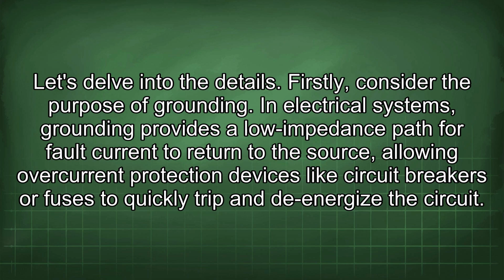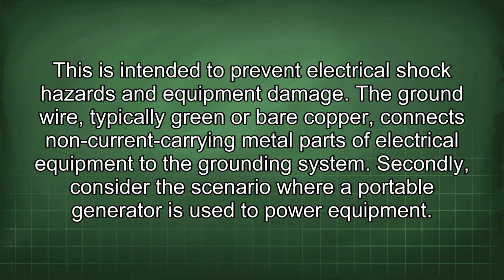Firstly, consider the purpose of grounding. In electrical systems, grounding provides a low impedance path for fault current to return to the source, allowing overcurrent protection devices like circuit breakers or fuses to quickly trip and de-energize the circuit. This is intended to prevent electrical shock hazards and equipment damage. The ground wire, typically green or bare copper, connects non-current carrying metal parts of electrical equipment to the grounding system.